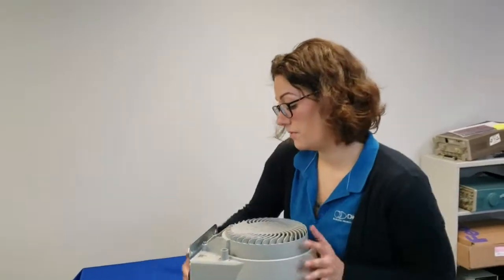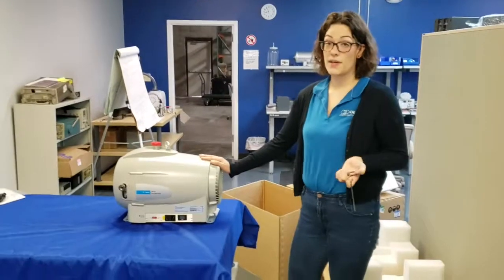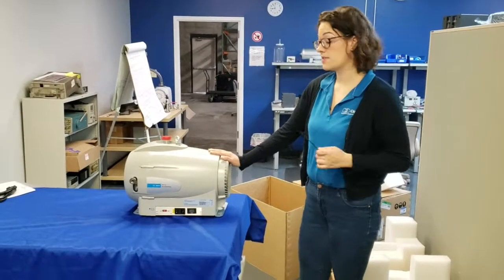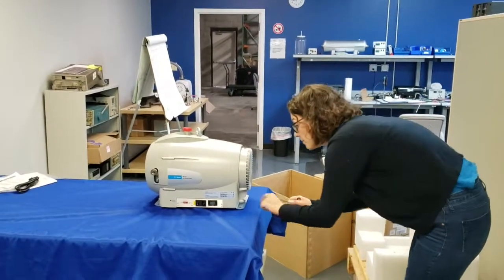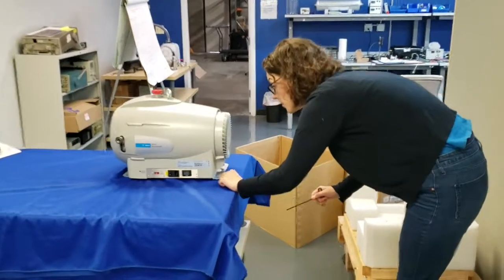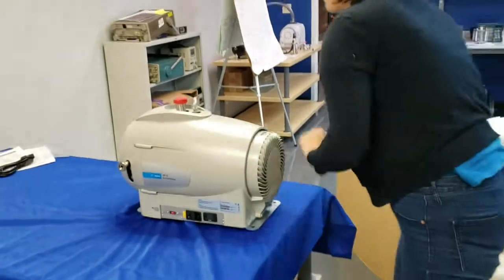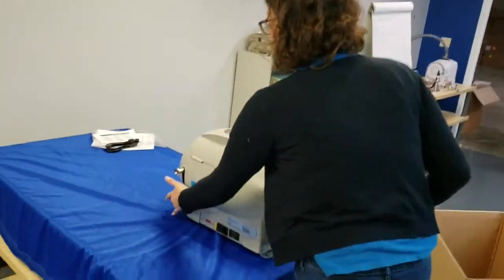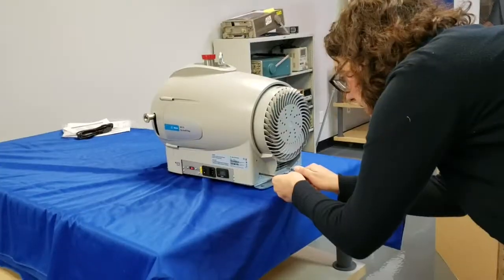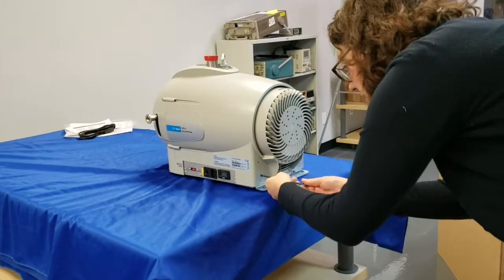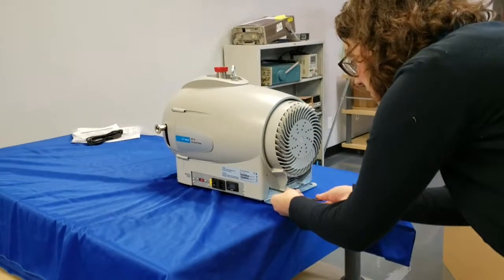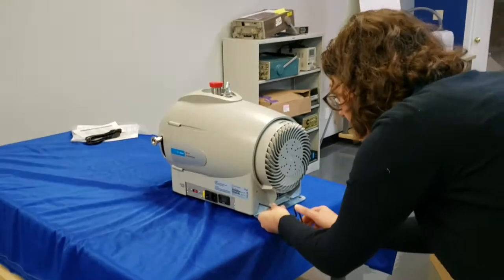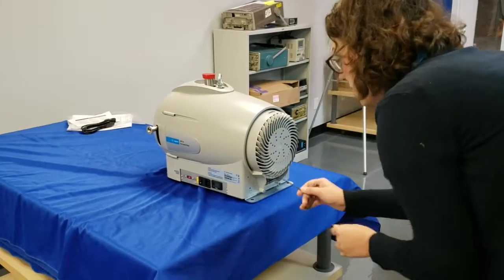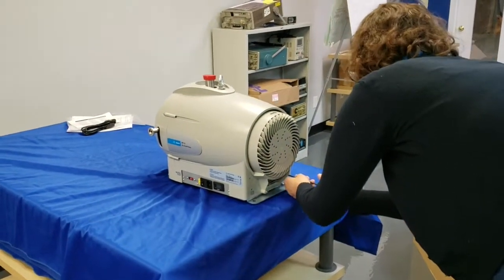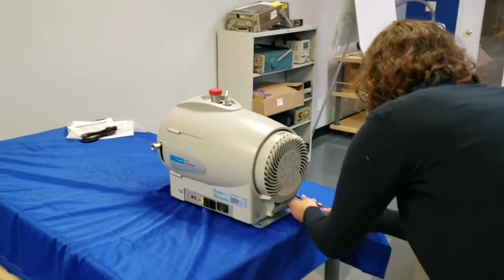Then we'll set the pump down, and it will rest on its rubber feet. Our next step is to disengage the shipping locks to loosen the floating feet inside. There are 4 shipping locks on the pump, on all 4 corners. We'll use the same multi-purpose tool, turning clockwise to disengage the feet just until you feel a bit of resistance, and then that shipping lock is disengaged. We'll do the same to each of the 4 shipping locks.